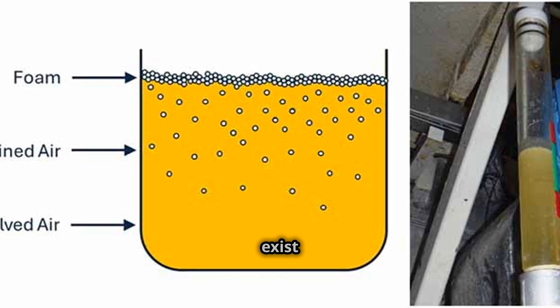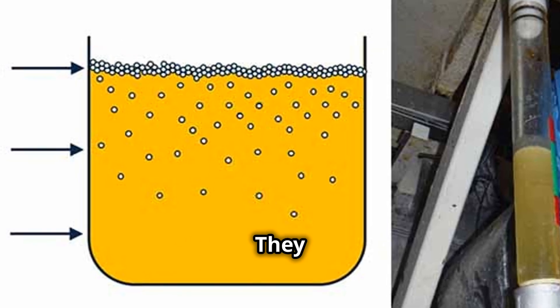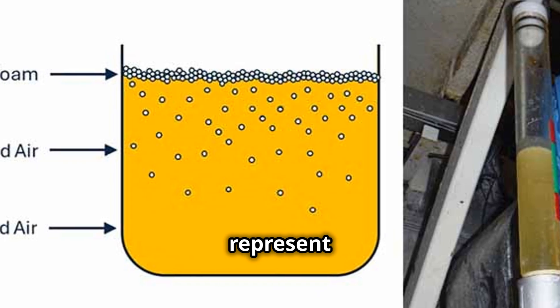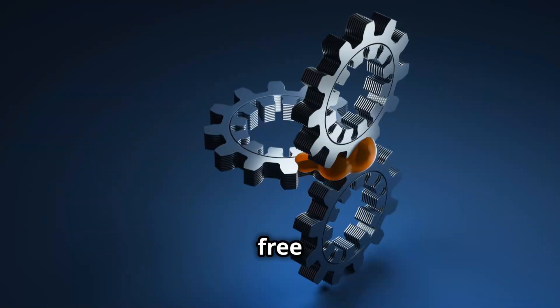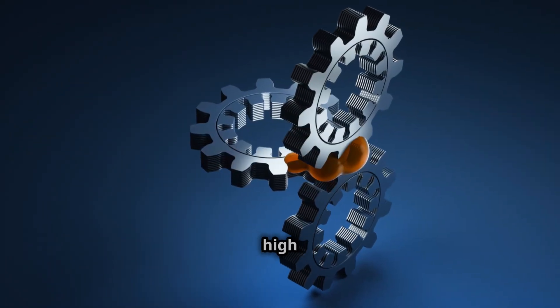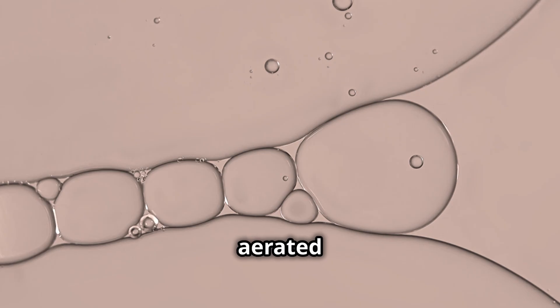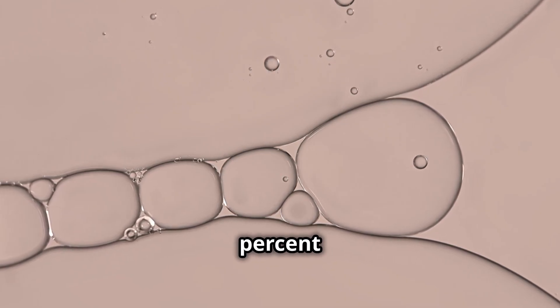Air can exist in oil in four different states of coexistence: dissolved — not visible, with no clouding present, and can represent as much as 10% of the total volume; entrained — unstable microscopic air bubbles with clouding present; free — trapped pockets of air in dead zones, high regions, and standpipes; and foam — highly aerated tank and sump fluid surfaces with more than 30% air.